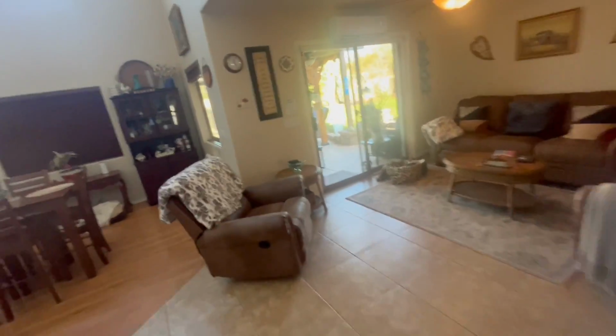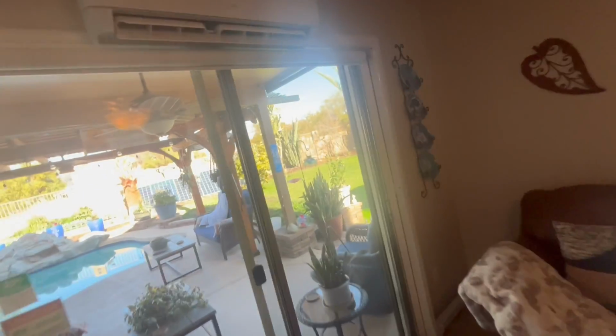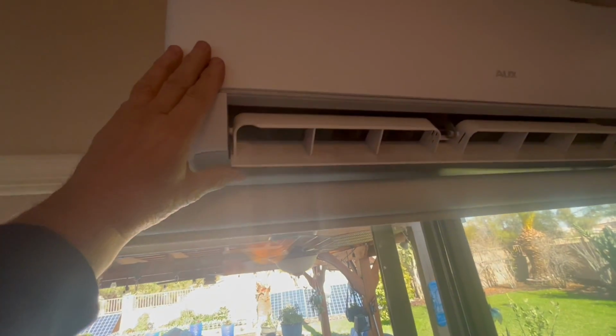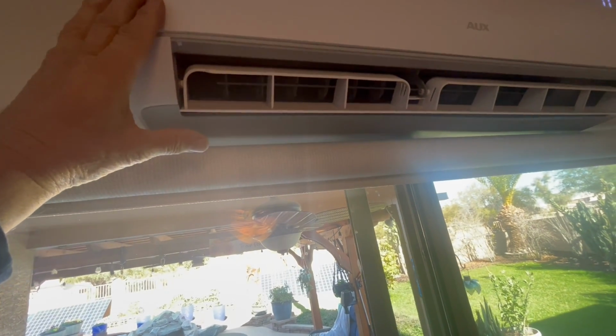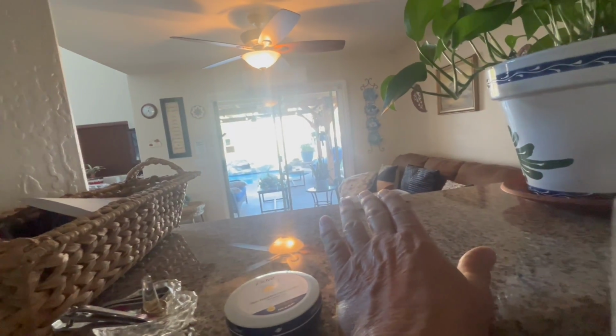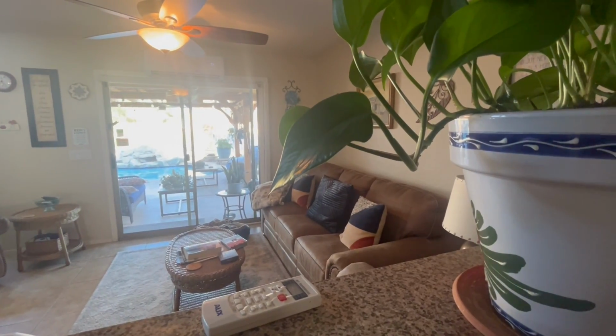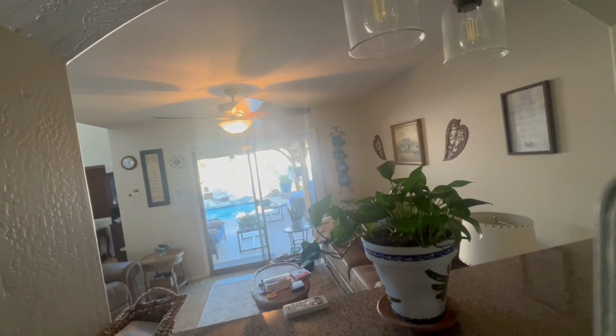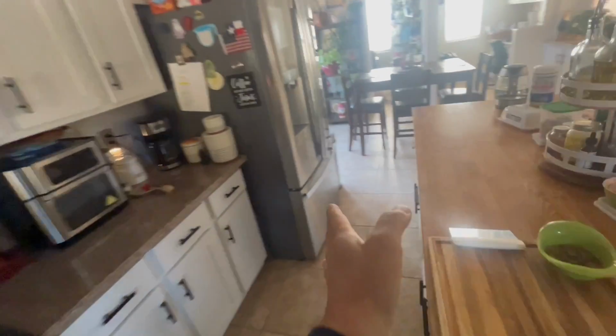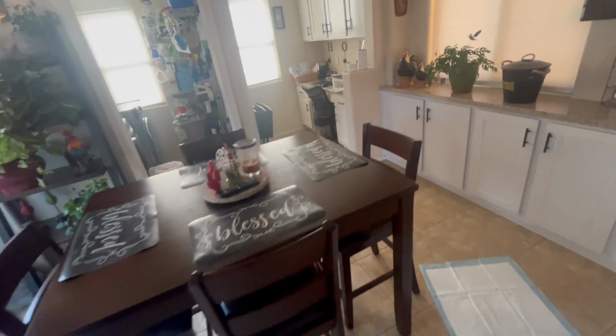And one of the things about these mini splits, like the aux one over here, is I can manipulate this. Earlier I said if you do that, it'll shut down. But see, it's at that angle right there. I could actually put it up about 3/4 of an inch. And remember, hot air rises, so you want it to drop. So right around there, you can see it's actually hitting the leaves. So by manipulating that and pressing that up 3/4 of an inch, and that's about all I can do, it'll actually blow down here and blow towards the floor. And as it does, it's rising towards the ceiling.